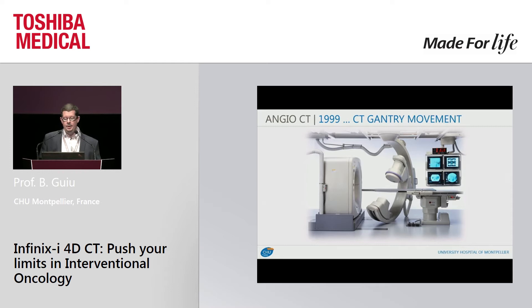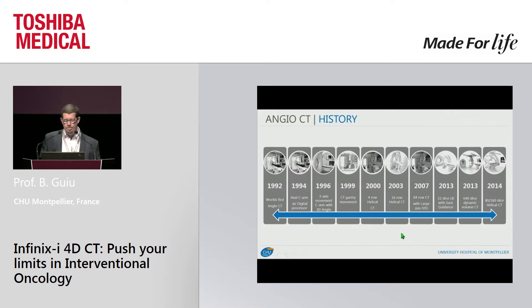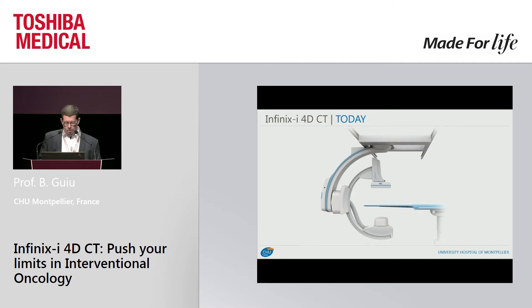With time, this technology evolved. In 1999, the CT gantry was moving on rails, and the C-arm had a multi-axis technology. From 2000 onwards, many evolutions occurred, essentially on the CT scan — 4 rows, 16 rows, 64 rows, and the famous 640-slice CT in 2013. This technology was essentially for Asian countries, mainly Japan. In 2015, Toshiba decided to launch this system outside Japan.